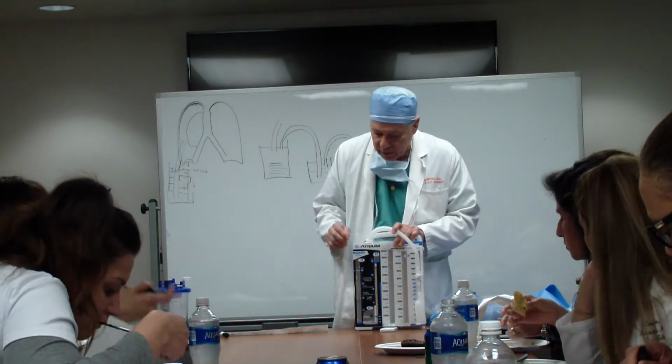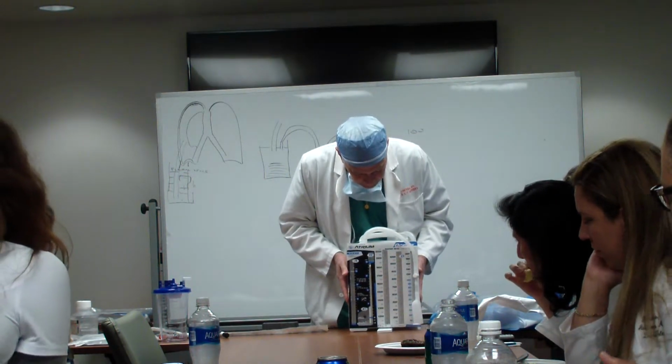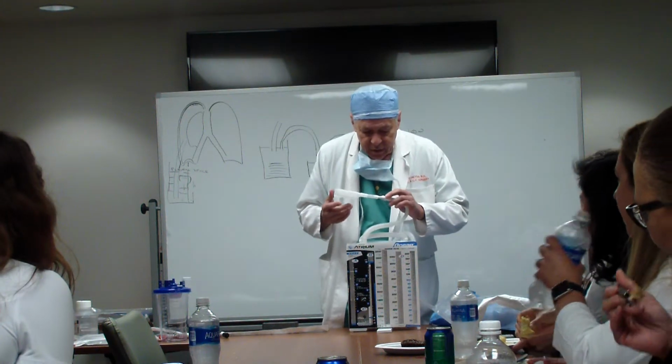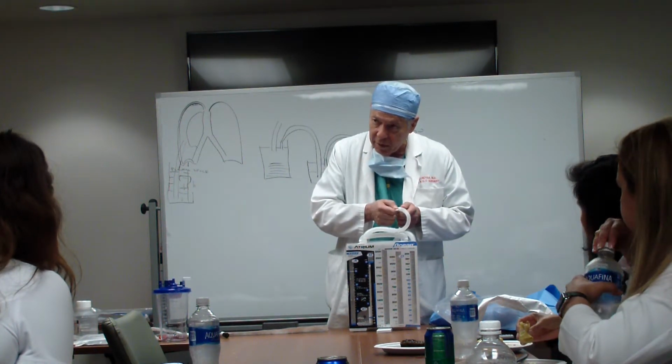The other thing is that I have seen the nurses regulating the negative pressure here. You can't regulate, you shouldn't regulate. It should always be open, always open, regulating at the wall.